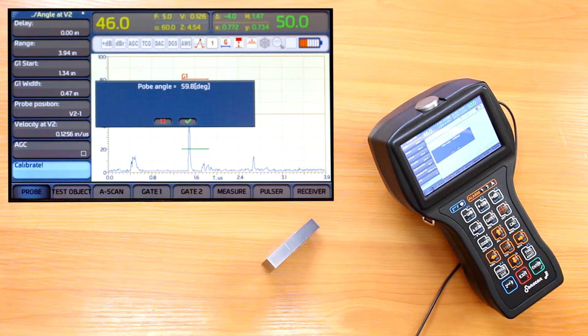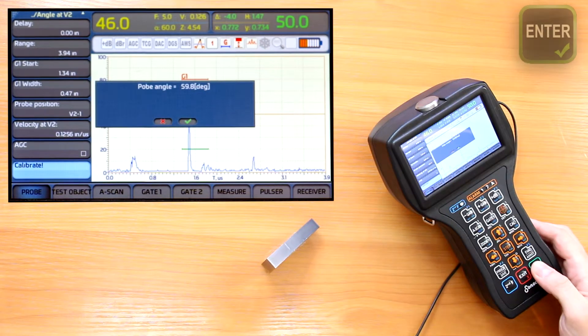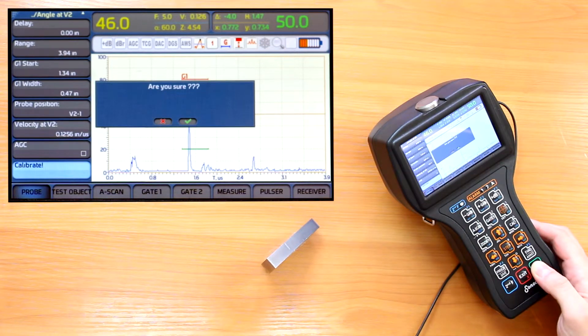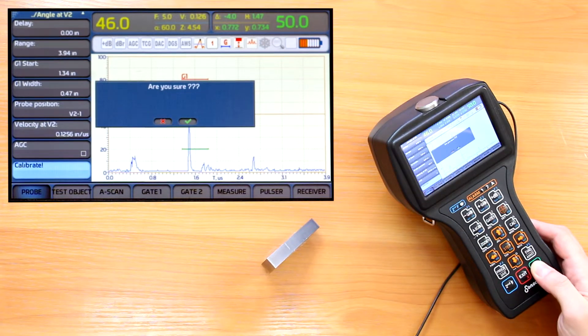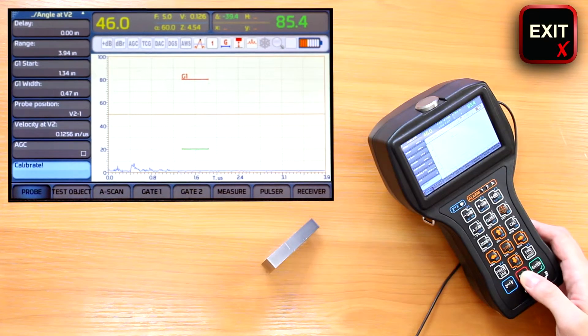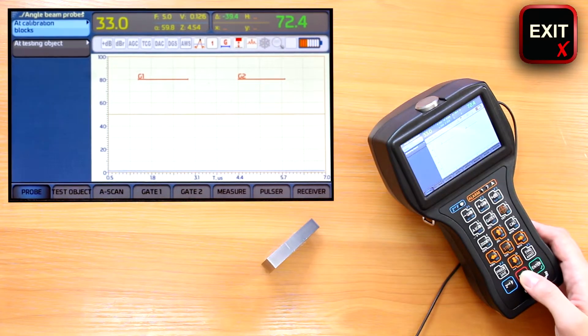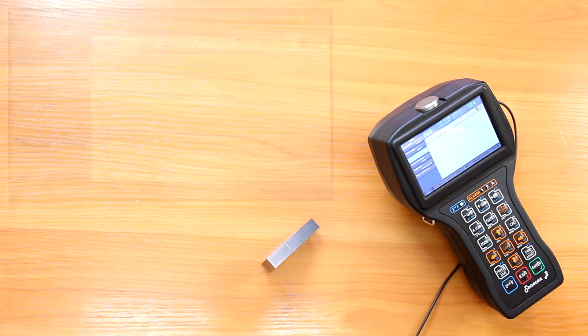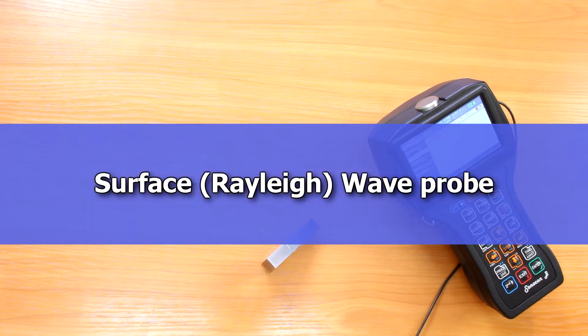The device shows the calculated value of the probe angle. We confirm it with the enter button. It then asks if we wish to save this value, so we press enter to confirm it. Triple pressing of the exit button takes us out of the calibration menus.